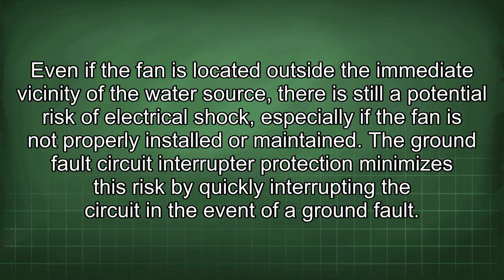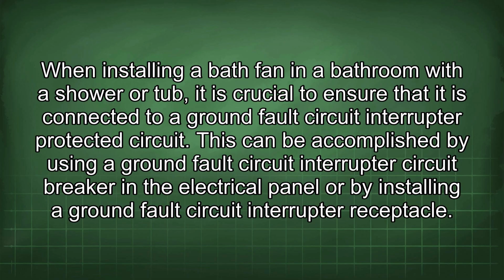Even if the fan is located outside the immediate vicinity of the water source, there is still a potential risk of electrical shock, especially if the fan is not properly installed or maintained. The ground fault circuit interrupter protection minimizes this risk by quickly interrupting the circuit in the event of a ground fault. When installing a bath fan in a bathroom with a shower or tub, it is crucial to ensure that it is connected to a ground fault circuit interrupter protected circuit. This can be accomplished by using a ground fault circuit interrupter circuit breaker in the electrical panel or by installing a ground fault circuit interrupter receptacle.